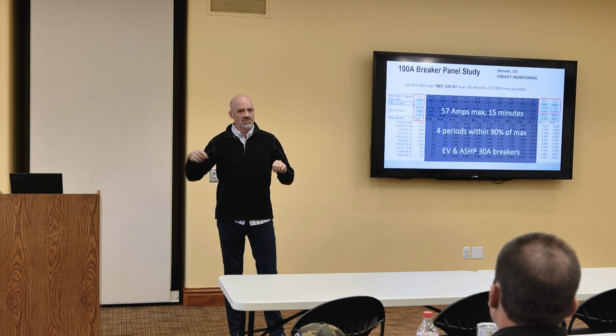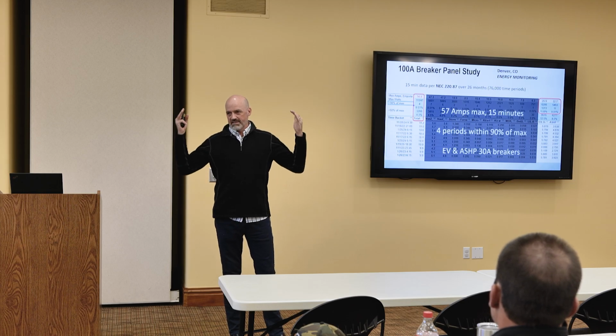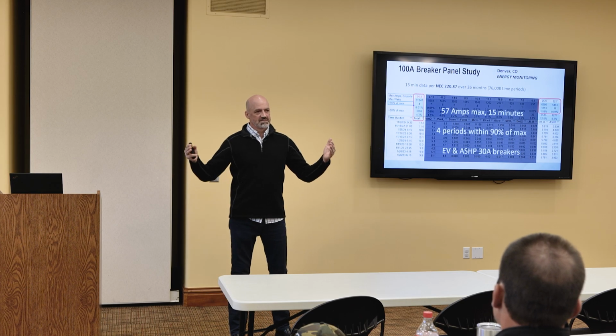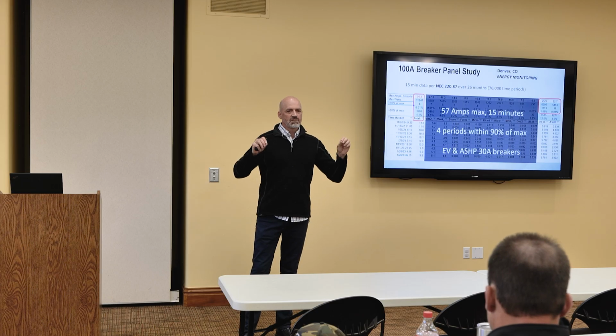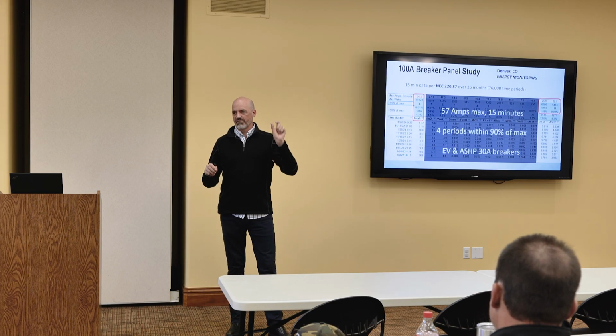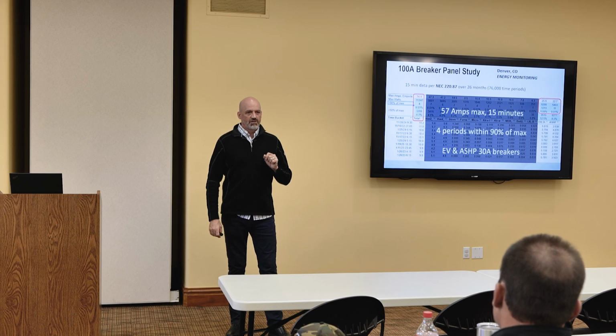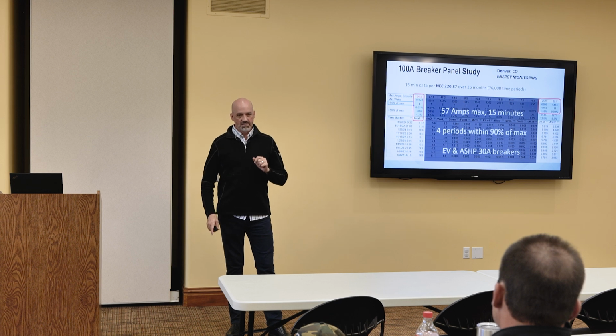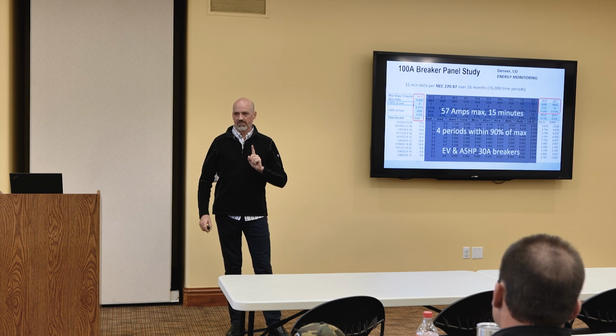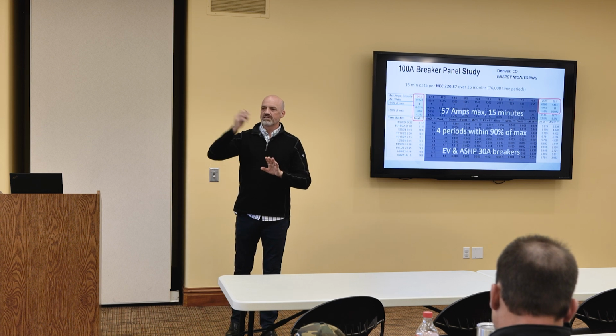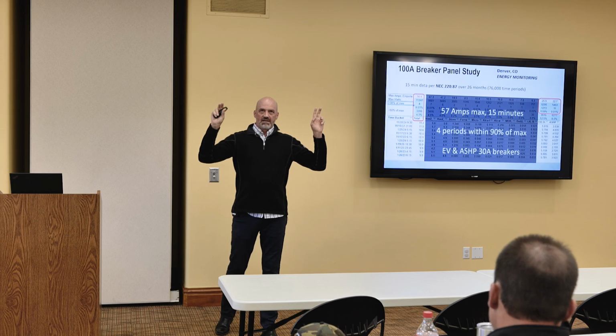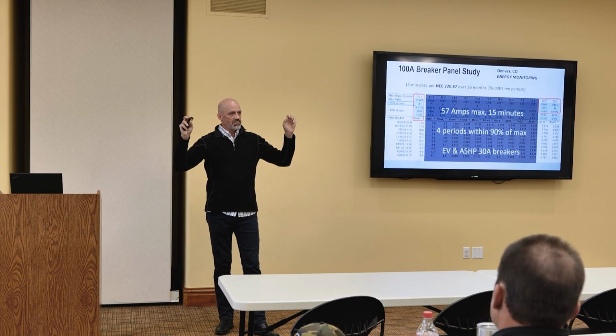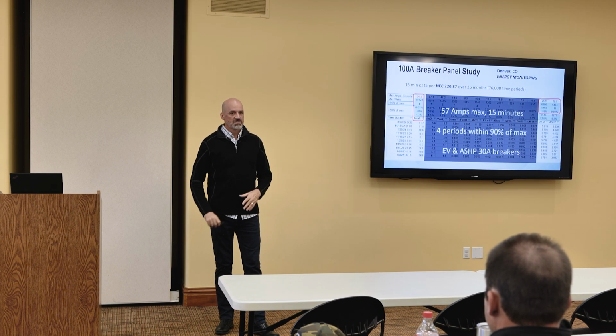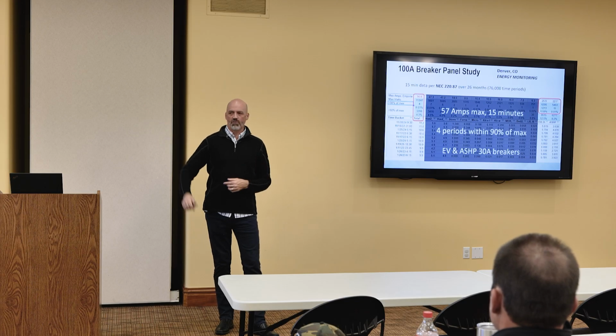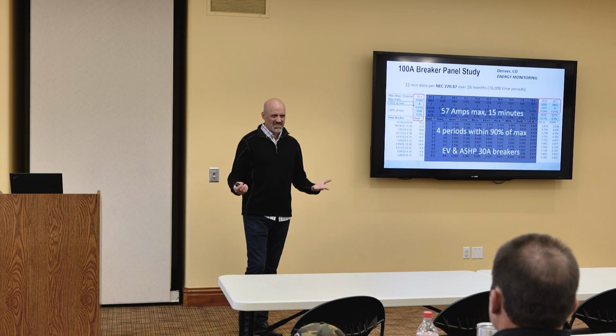Those 3 panels are span panels, and we looked at 6 months of data on it. The absolute worst 15 minutes was 99 amps. They could have handled that entire house comfortably with one span panel that could load shed easily up to sort of an equivalent 300 amp type of a service, and they were nowhere near the 400 they were rated for.